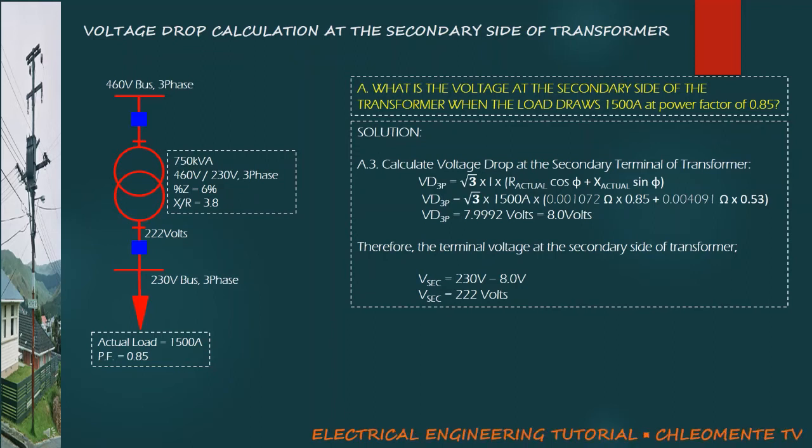Therefore, the terminal voltage at the secondary side of transformer is 230 volts, which is the rated voltage of the transformer, minus the voltage drop of 8 volts, yields to 222 volts.